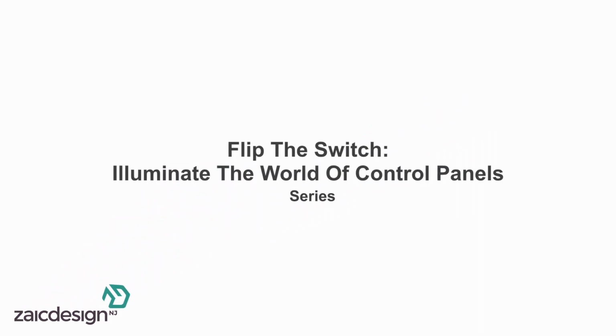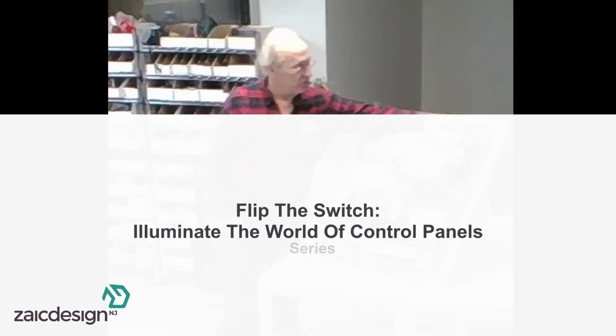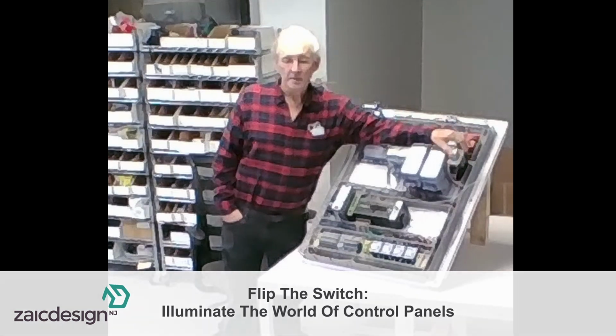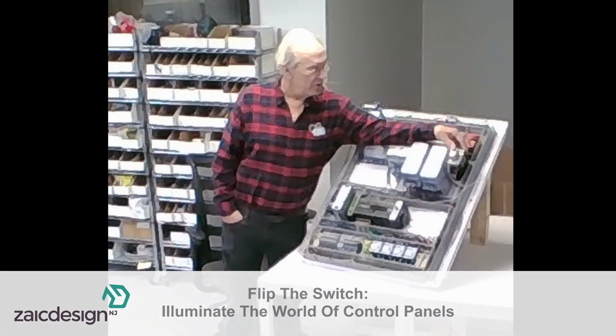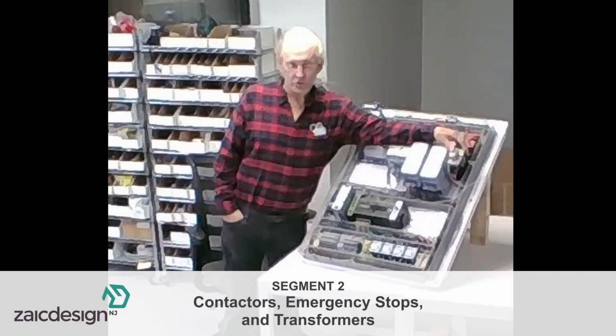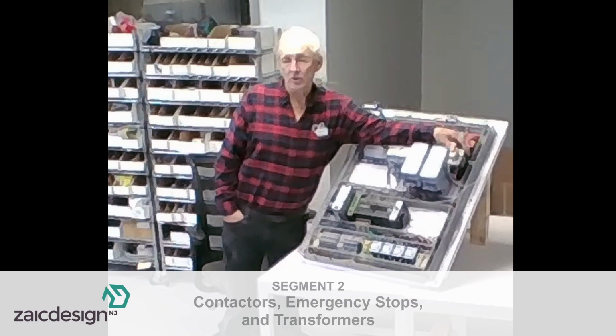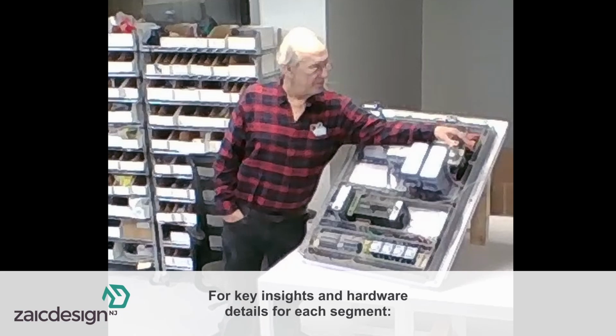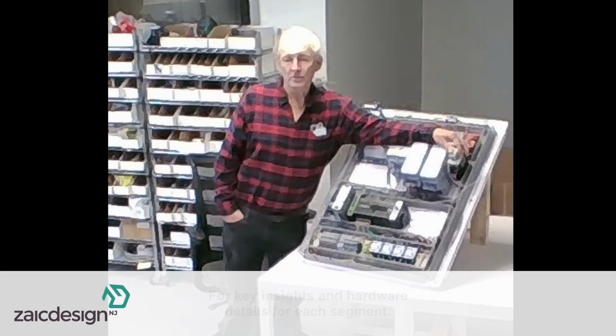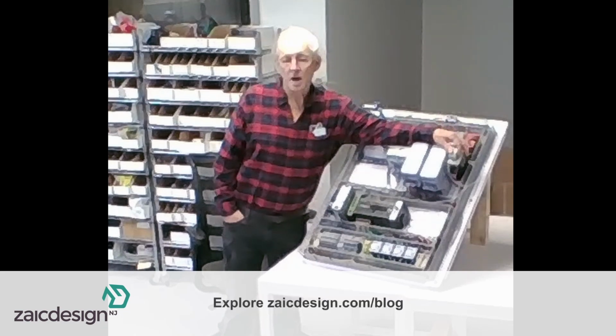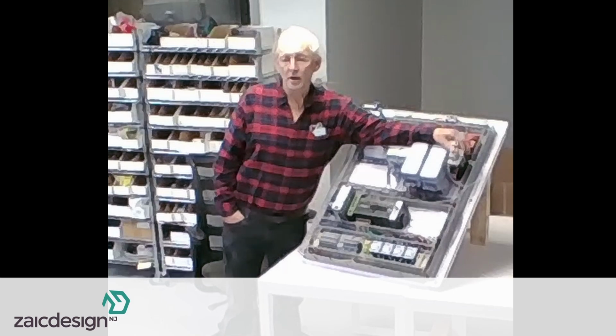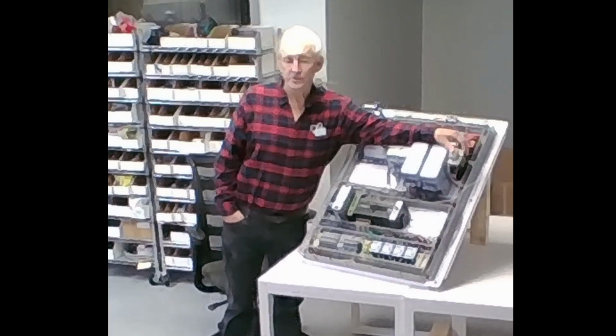Okay, so the power then always goes to a main contactor. The main contactor is an electrically operated switch that can break the power, okay? And the main contactor is part of the emergency circuit. So the e-stop is what energizes and de-energizes the main contactor, okay?